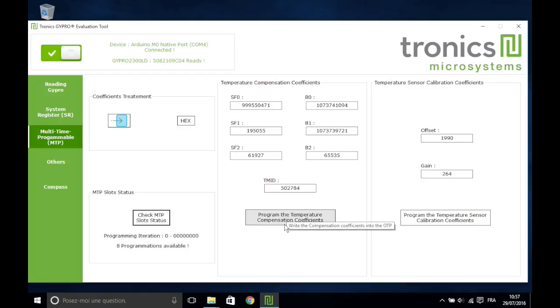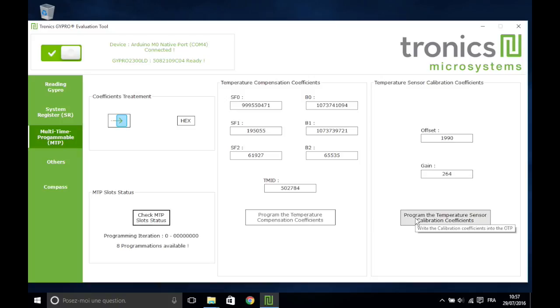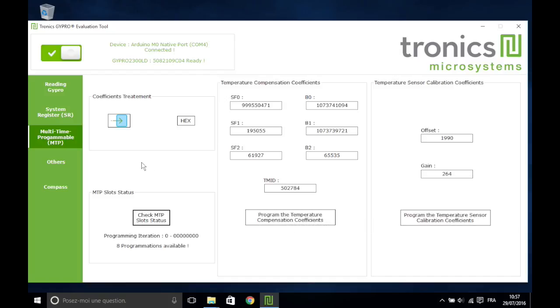Be careful, this operation creates permanent writing into sensor memory. For the temperature sensor calibration, you have only one programming slot, so clicking on the Program button is irreversible.